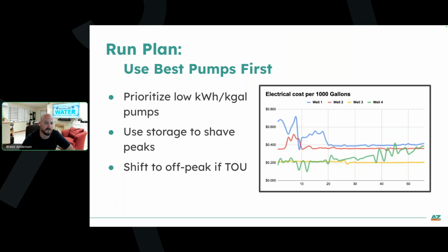Don't forget, if you are going to look at doing like lag and lead functions, that you really want to alternate those lag pumps so they are getting some movement on the bearings. You want to keep them healthy, but you don't necessarily have to have them running constantly with everything on, everything off, because you're going to end up burning up money just running your inefficient units.